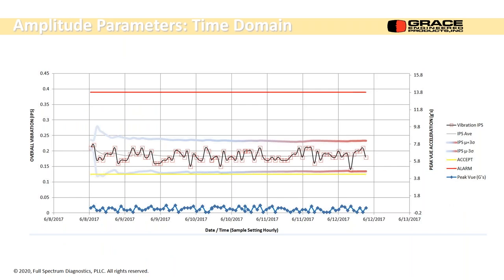And we've been talking around this the last couple of seminars, webinars. This is about 4 days worth of data and phenomenal trend changes. Amplitudes are very simple, mean plus three sigma vibration. And what that means is the mean vibration plus or minus three standard deviations from that mean. And we can have lots of different statistical alarms on this.